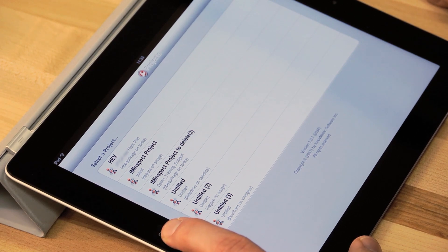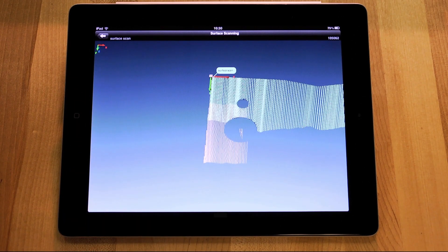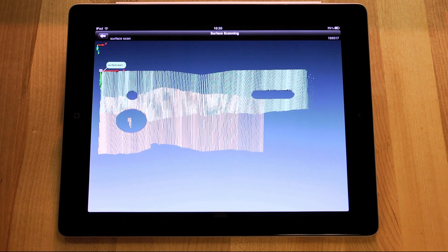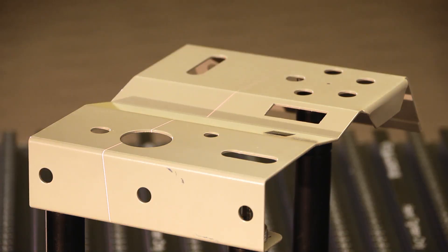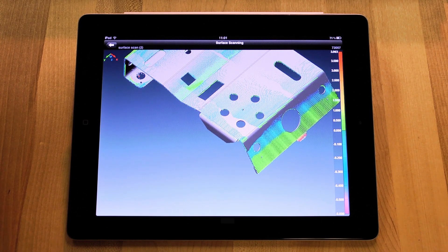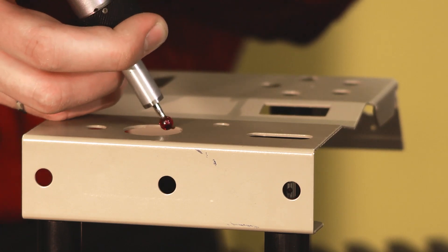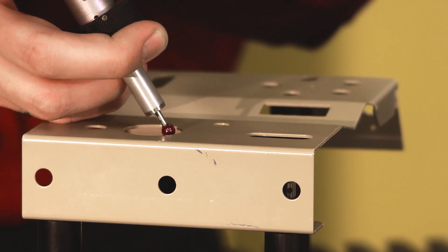Now let's take a closer look at the 3D scene display mode, which helps you see laser scans directly on the mobile device while they are being captured. You'll even be able to do real-time comparison to a reference model while scanning, and when probing, the 3D scene display mode gives you intelligent visual guidance so that you can probe specific areas with better visual feedback.